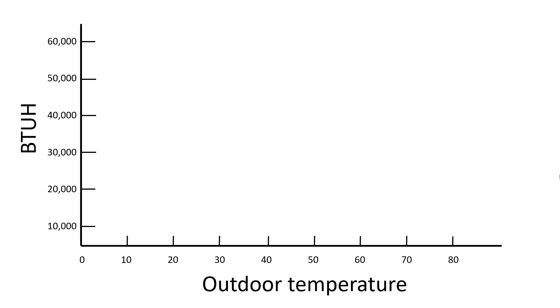First we need to do a heat loss calculation for the house. Here in Seattle we use a delta T of 50, so we're looking at an outdoor temperature of 20. So we're going to draw a line straight up from 20 degrees and we've calculated the heat loss on this house. We're going to say 40,000 BTUs per hour when it is 20 degrees outside.